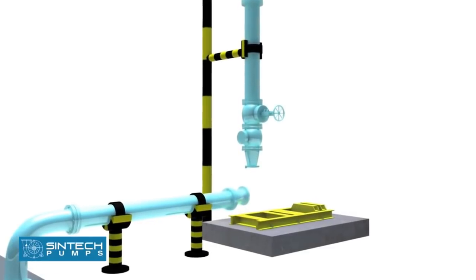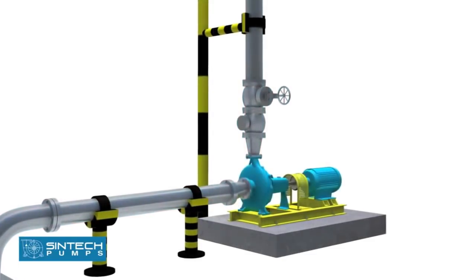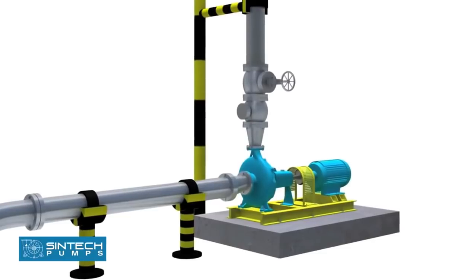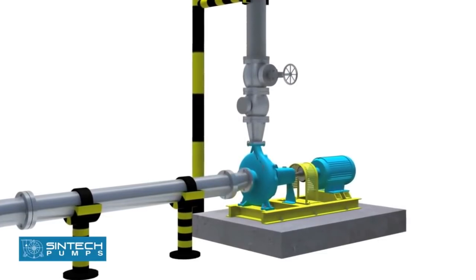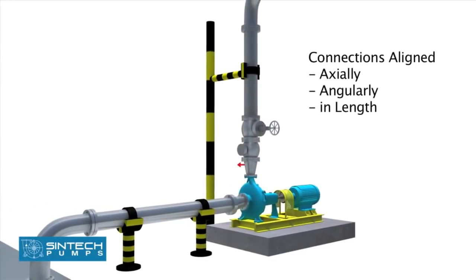When the pipes are not supported, their weight is borne by the pump casing and may cause them to crack or deflect. It is important that the connections be carefully aligned axially and angularly.